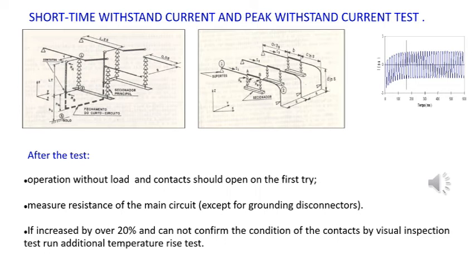Here we present the short time withstand current and peak withstand current test. This is a very important test and one of the most expensive tests that we have in the standards, because the mountings are big to do and take some time to mount.